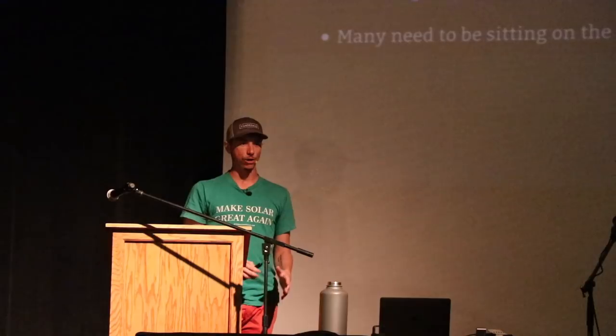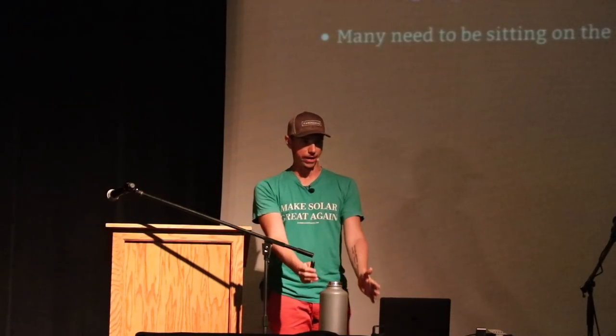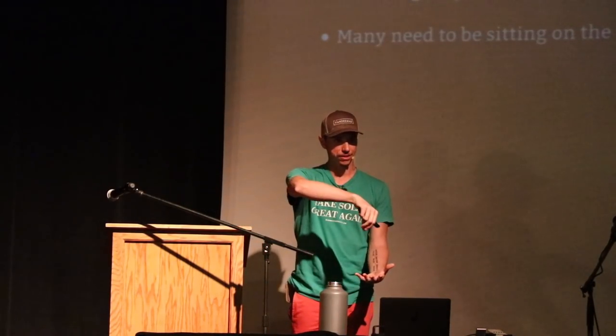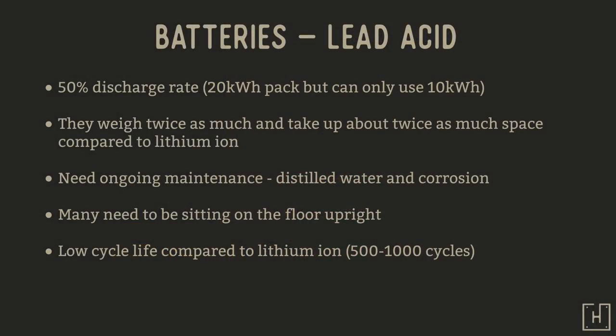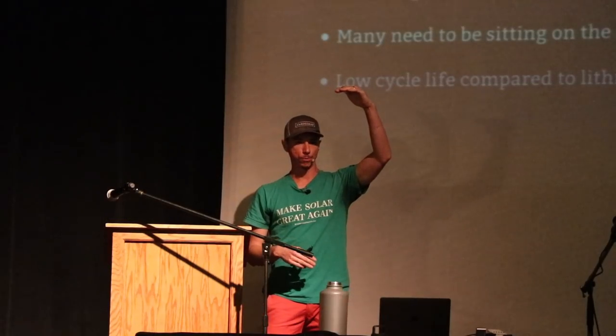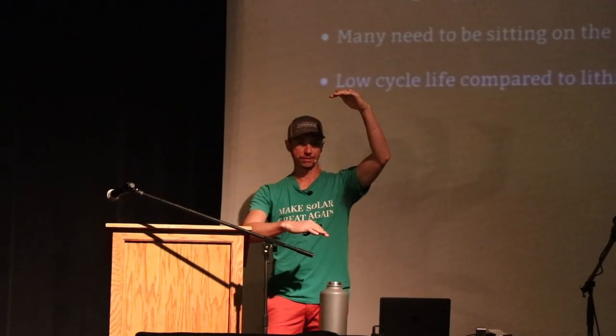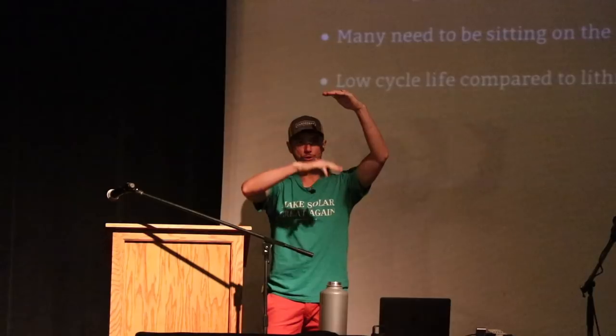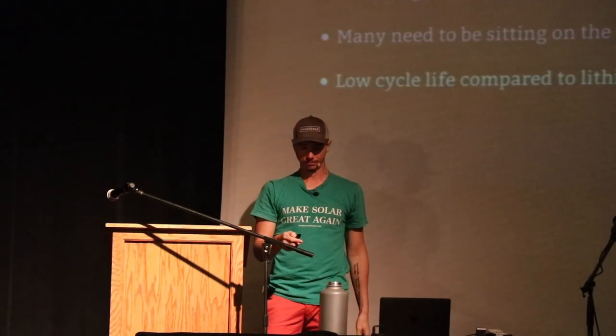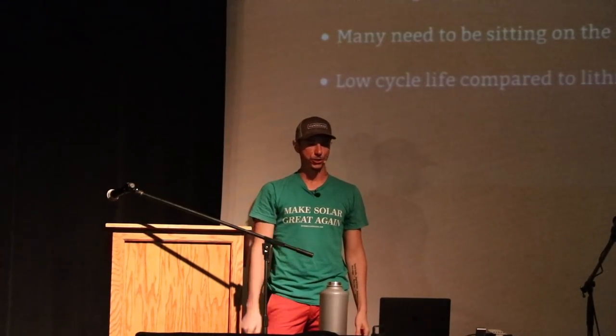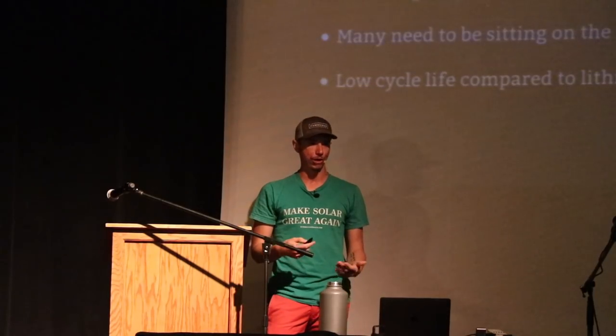Many of these batteries also need to be sitting on the floor upright, because they are filled with water and you have to top them up with water. They have a low cycle life compared to lithium ion. What is considered one cycle is when you have them fully charged at 100%, bring them down to 50% — that is considered a cycle when it goes through that range. So they only last between 500 to 1,000 cycles before they get to a point where you're going to need to replace them.